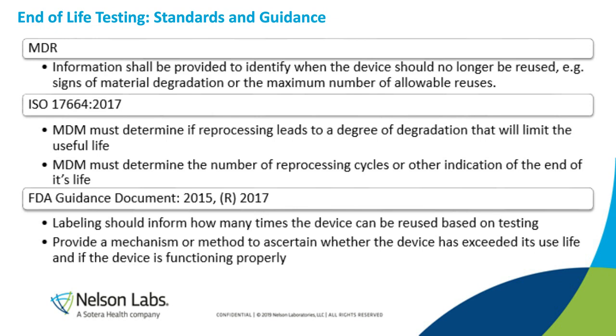So at this point, medical device manufacturers normally specify verbiage that shows when the device is degraded enough to show that it's at the end of its life. Now going forward with the requirement of the unique device identification, that will allow healthcare facilities and thus medical device manufacturers to determine a number of reprocessing cycles that will show that the device is at the end of its life.